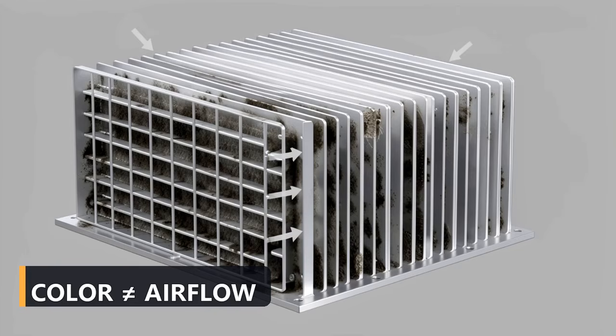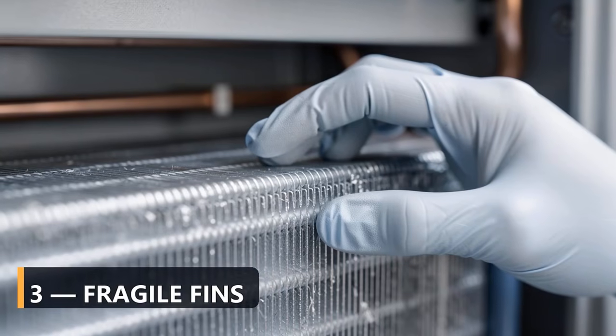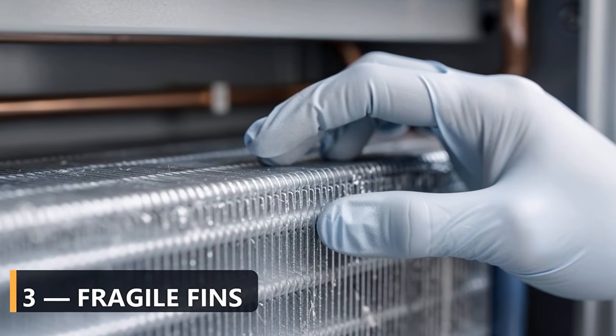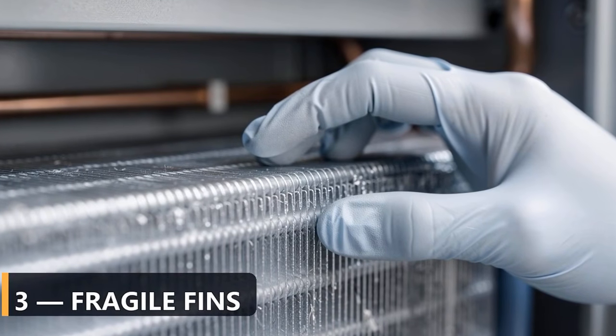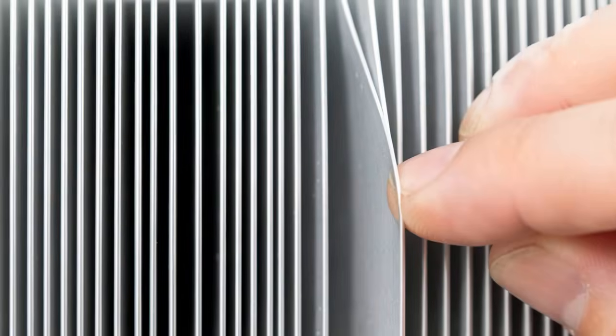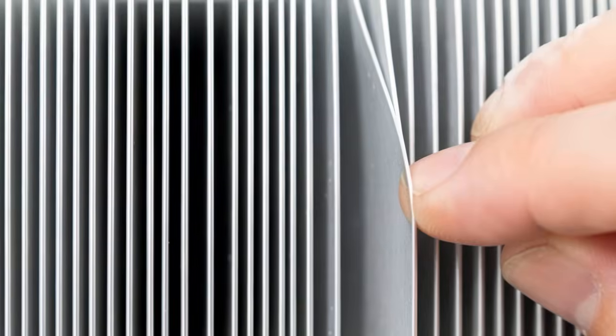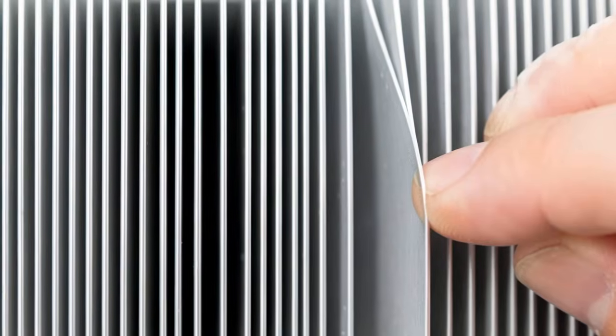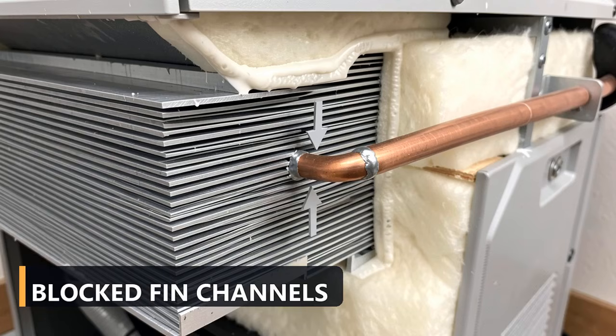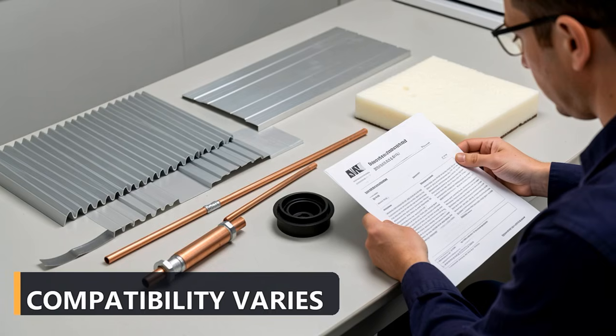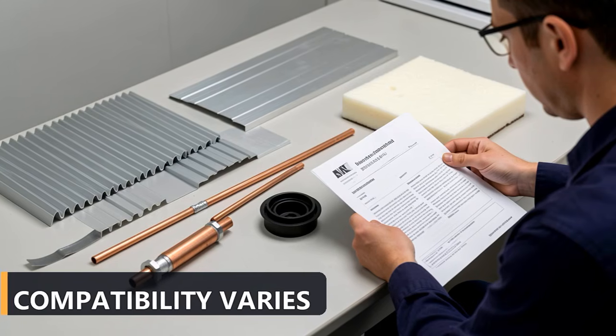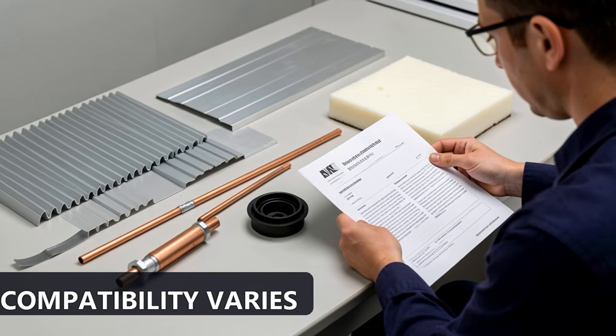Number 3. Those shiny fins are much easier to damage than they appear. Evaporator fins can bend with surprisingly little pressure. A stiff brush, high-pressure spray, or aggressive wiping can flatten them into a wall that blocks air. The tubing, soldered connections, protective coatings, plastic drain pan, sealants, and cabinet insulation may all have different chemical compatibility limits. A cleaner that is acceptable for one coil is not automatically safe for another.